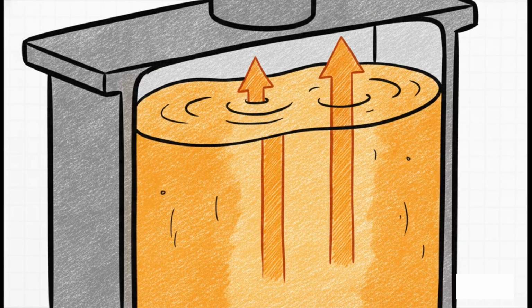And because of that intense heat, the insulating mineral oil doesn't just sit there. Governed by the strict laws of thermodynamics, it acts like a highly dynamic fluid. As the internal temperature climbs to that 95-degree mark, the oil literally expands in volume. The extra heat causes the overall oil level to slowly, steadily rise inside the main tank. We're talking about a massive amount of liquid swelling as the temperature goes up.